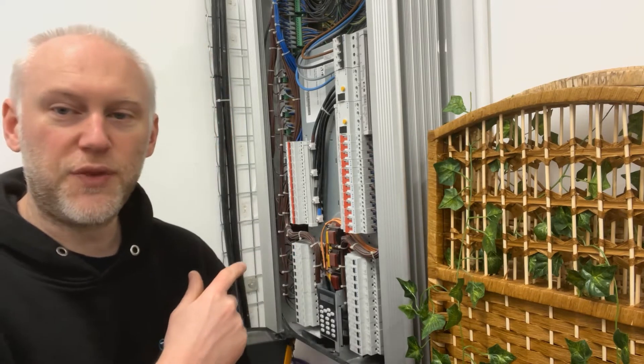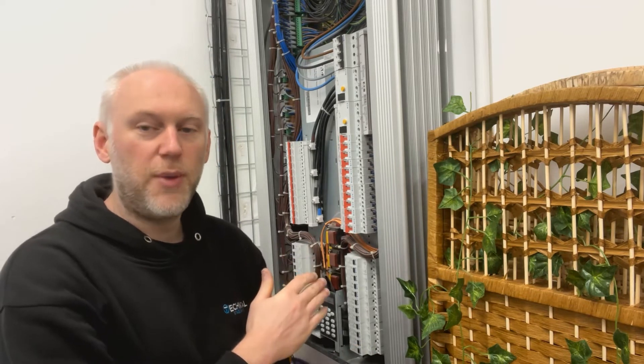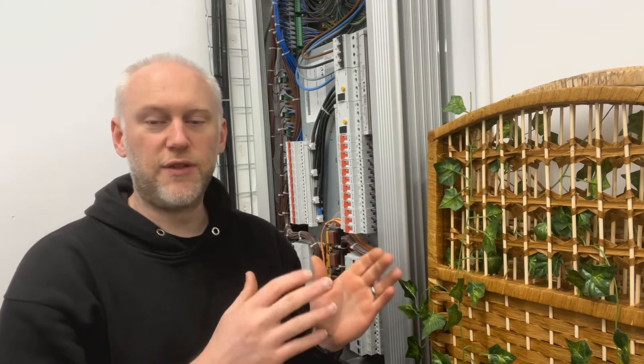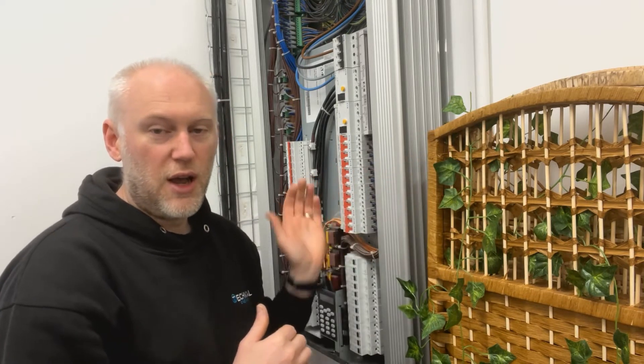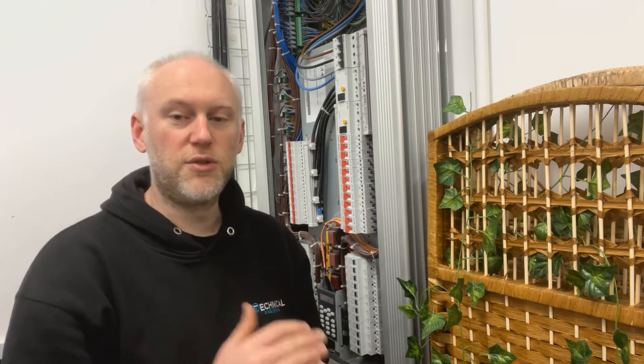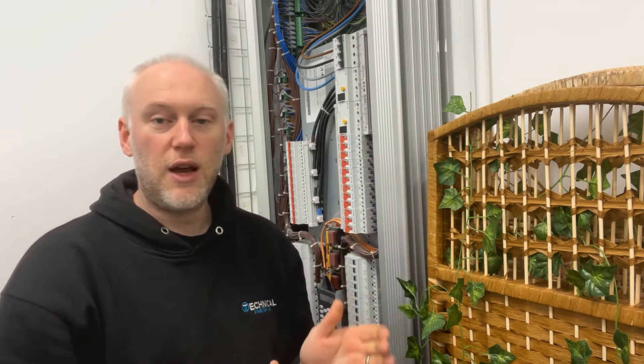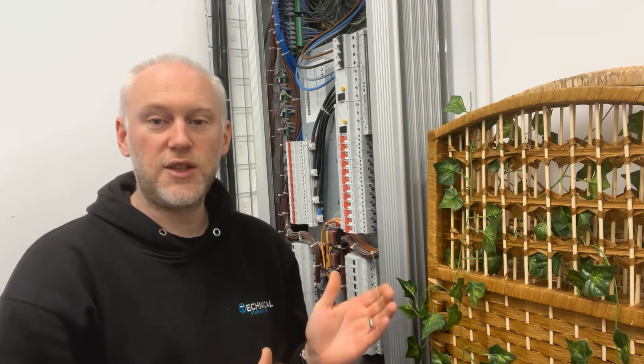Behind me we've got a dimmer rack — a quite standard dimmer rack. It's a Zero 88 Chilli rack, 24 channels. The nice thing about this is it's one of the bypass racks. We talk about dimmed power and hard power and the difference between the two. Dimmed power is for traditional lighting where a control desk varies the voltage to the light through a dimmer circuit. A lot of newer lights are intelligent and require a constant power supply — that's what we deem as hard power. This rack lets you change each individual channel from dimmed to hard power, so the same supply can serve both incandescent lights and intelligent lighting.